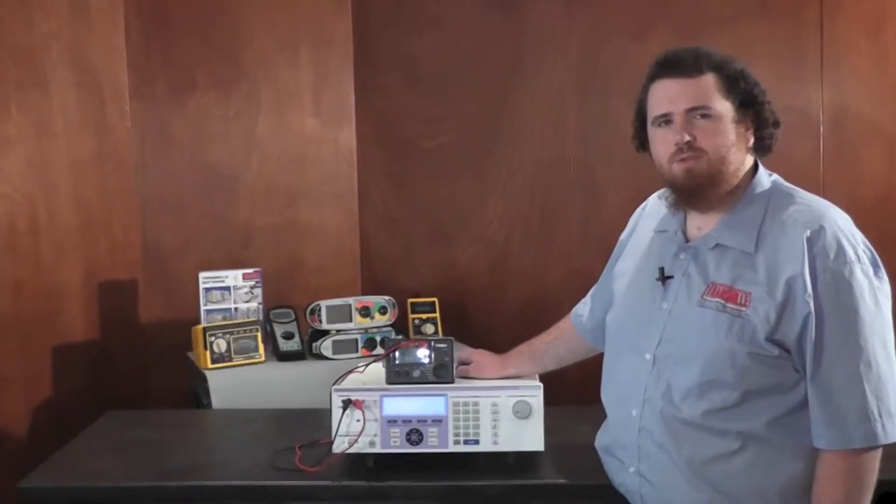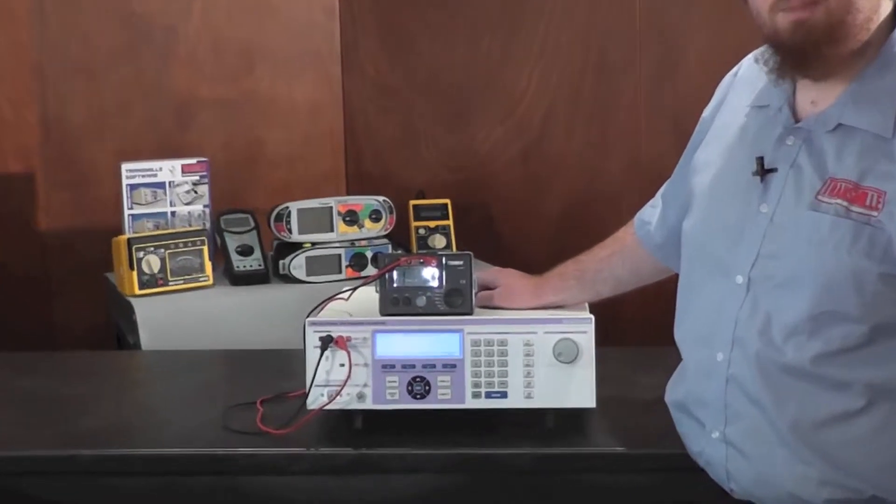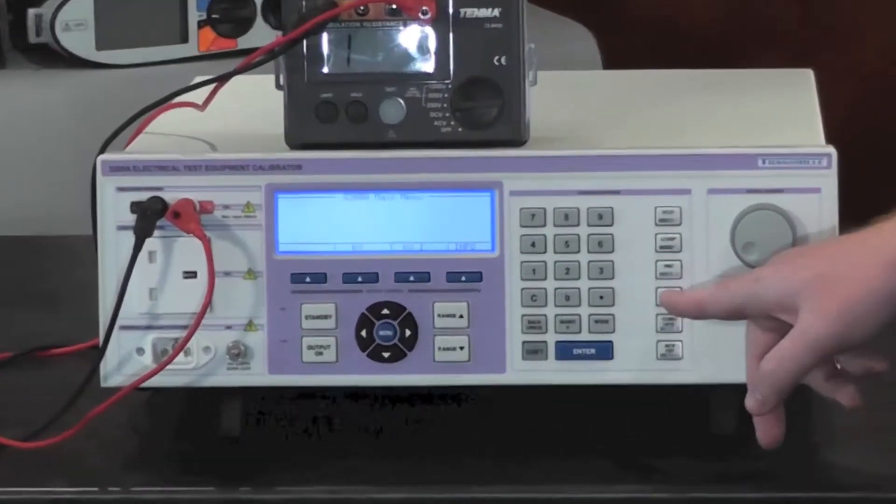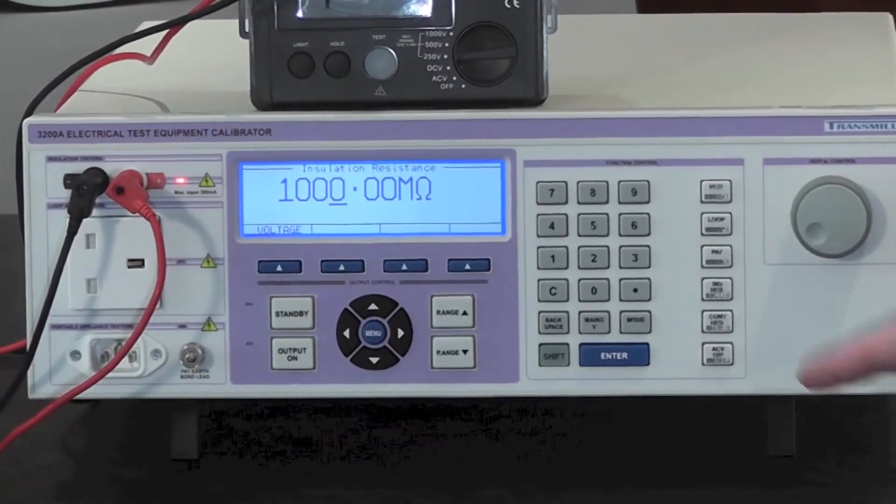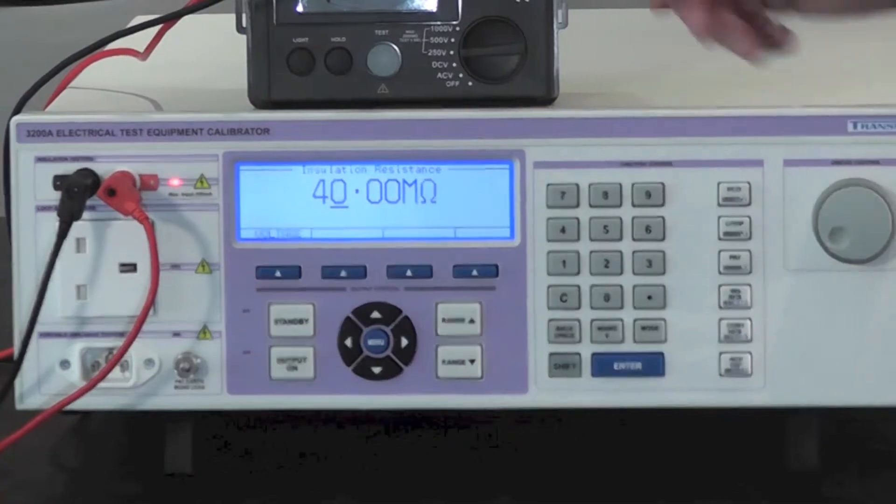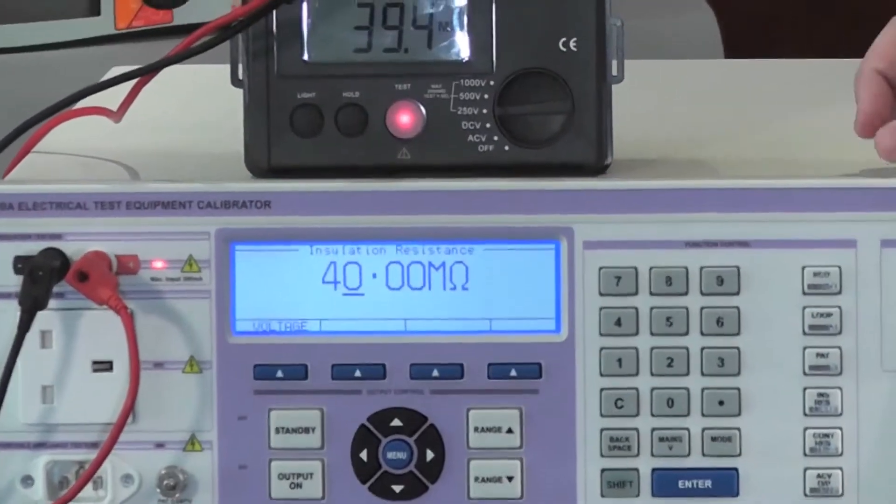Calibrating insulation testers with the 3200A couldn't be simpler. Simply select the insulation resistance function, enter the resistance required, for example 40 megaohms, and press the test button on the tester.